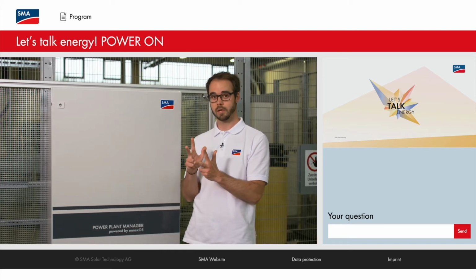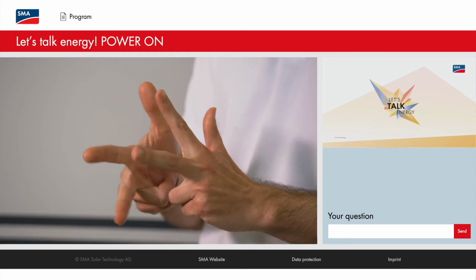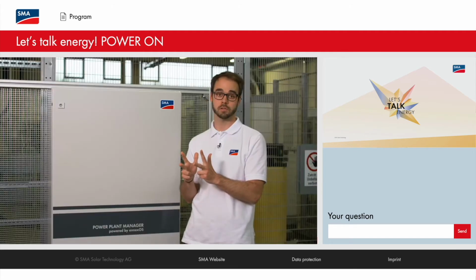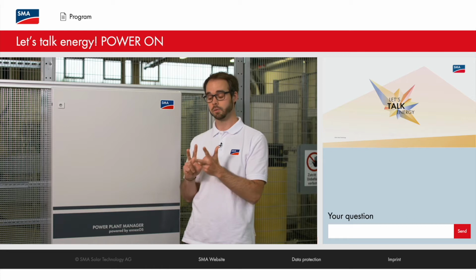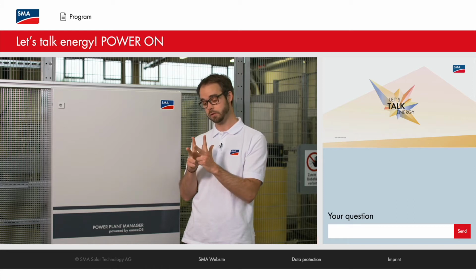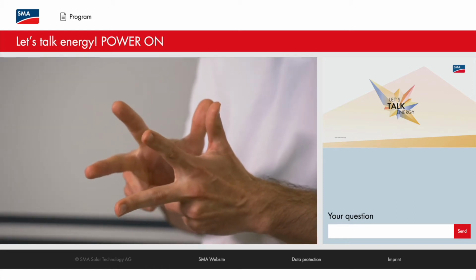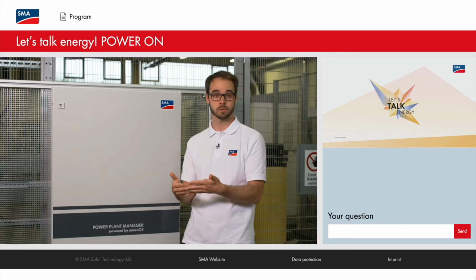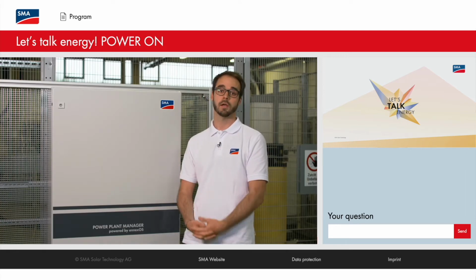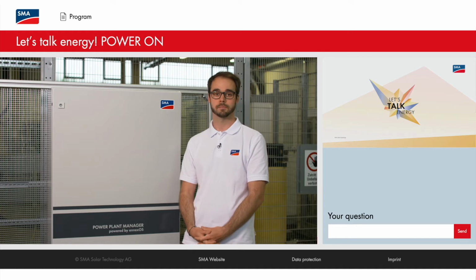This is a process you can estimate to be fairly complicated, because it's two power grids that have to be synchronized onto each other. There are two different voltage sources, two different frequencies, and you would have to synchronize those two grids onto each other, which takes a couple of seconds. Afterwards, when it's synchronized, you can close the switch and the system is grid tied again.